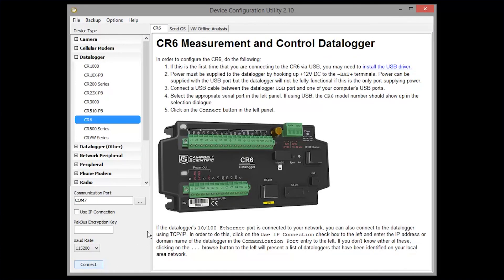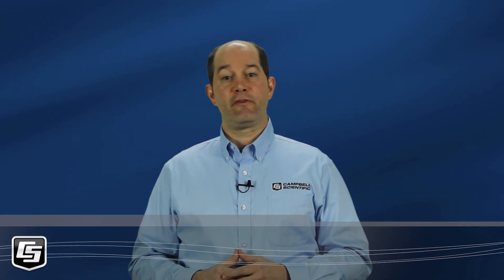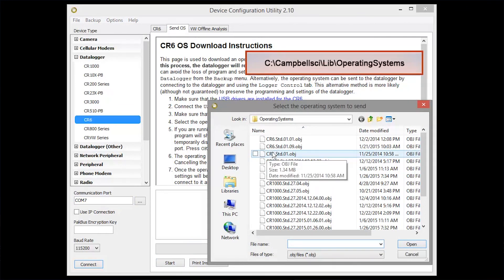Let's go back to the Send OS tab. All data and programs will be lost at this point — the data logger will be set back to its factory defaults. For CR Basic data loggers other than the CR6, you will need to remove power from the logger. Not cycling power for these loggers is one of the most common errors people make. Device Configuration is waiting for a sync byte that the data logger sends when it first powers up. Click Start, then navigate to the new OS. By default, it will be in the C:\Campbell Sci\Lib\Operating Systems folder.